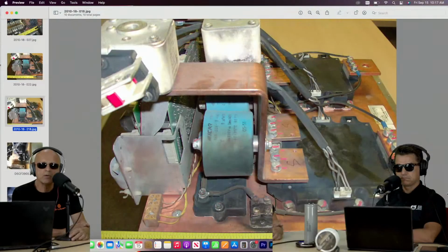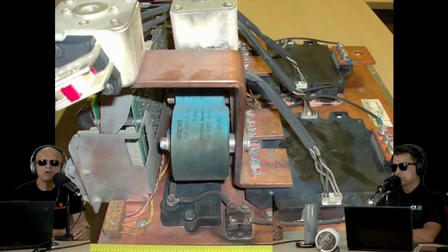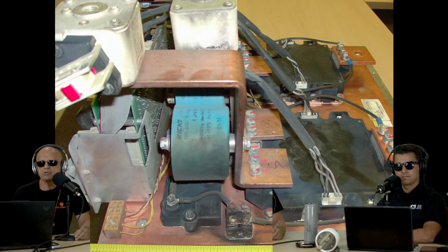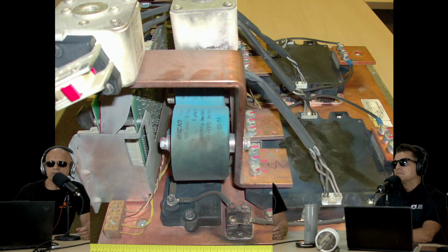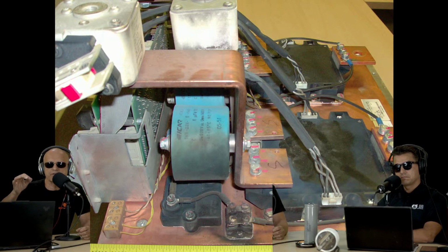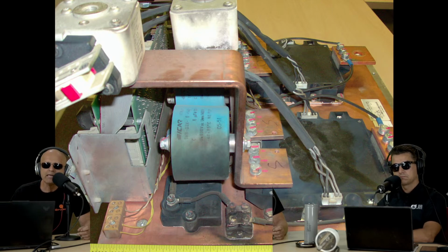Years ago, we had a large UPS system here, actually at a newspaper, a 600 kVA GE UPS, and it went down. We went in and it looked like lightning damage, but we're talking about arc flash here. If you look at that image, there's vaporized metal, that dark stuff, with a little shine where you can see metal flash. It actually ate up things like copper bus bars and bolts.